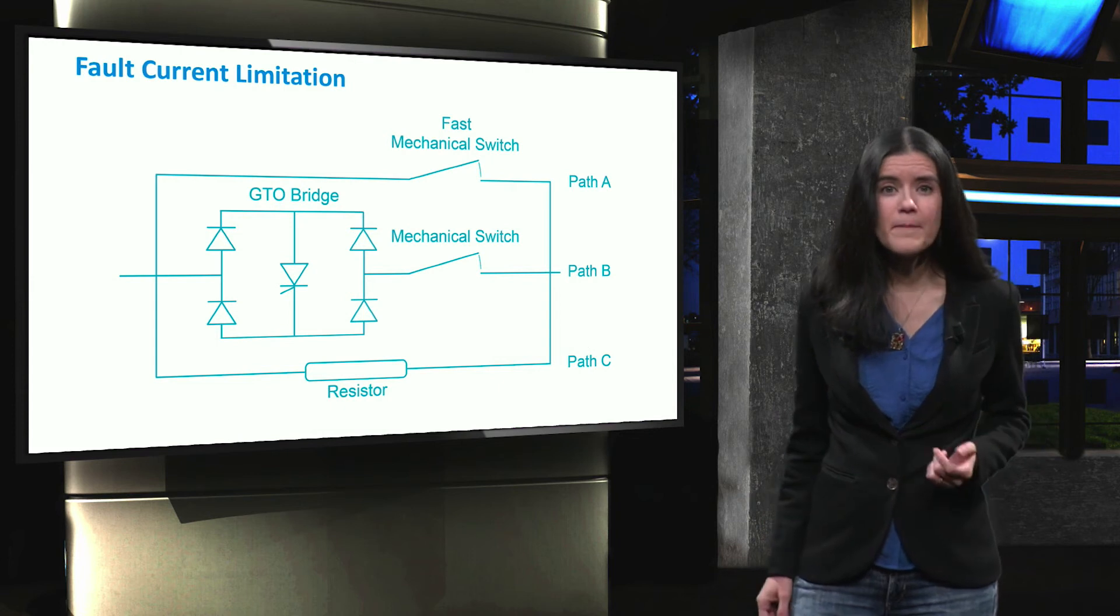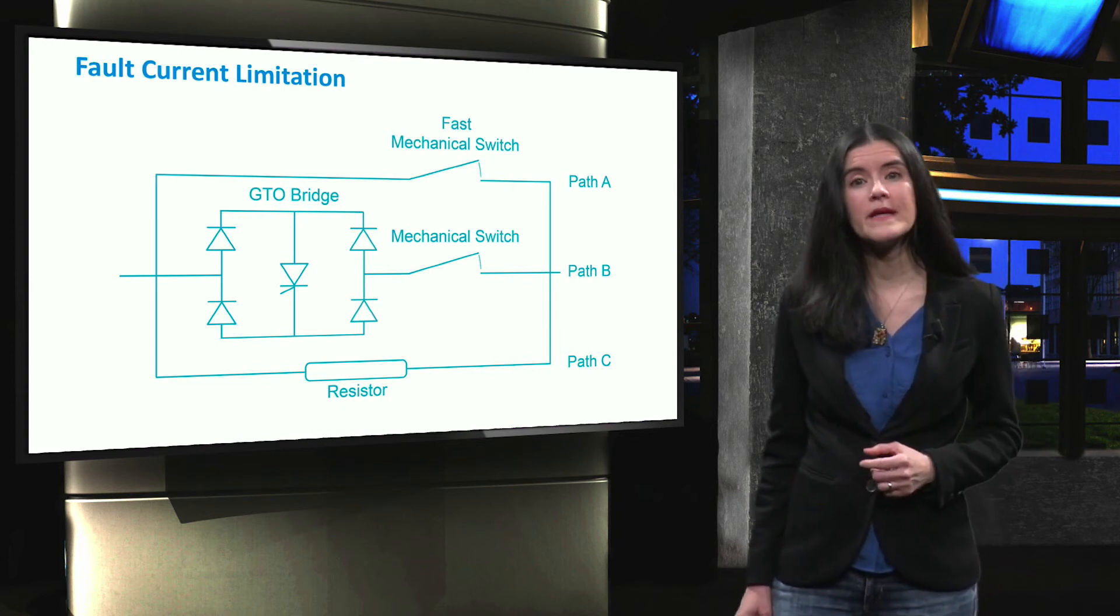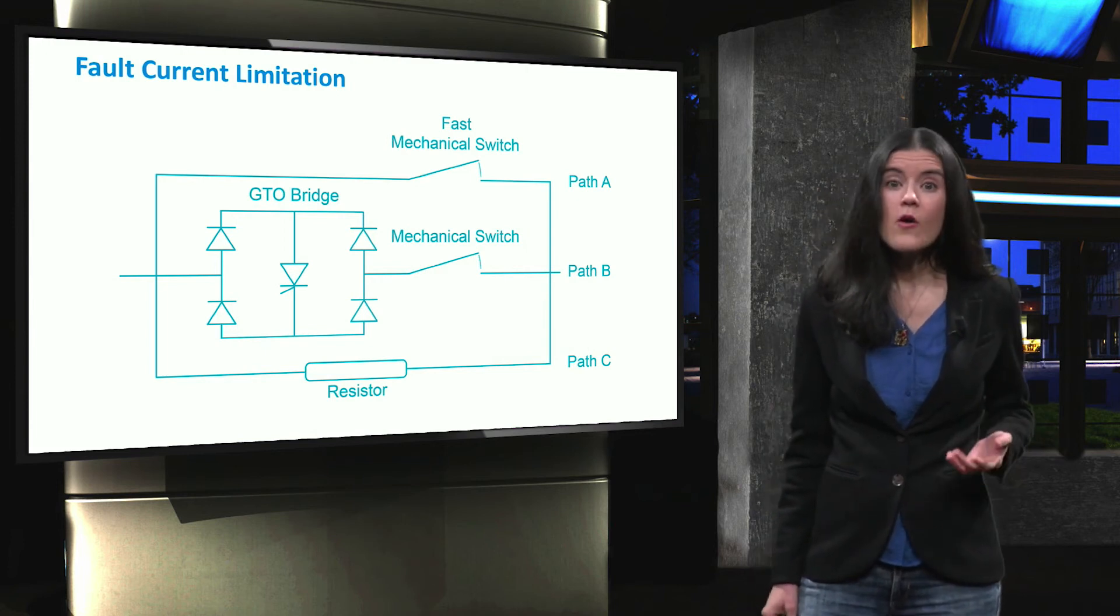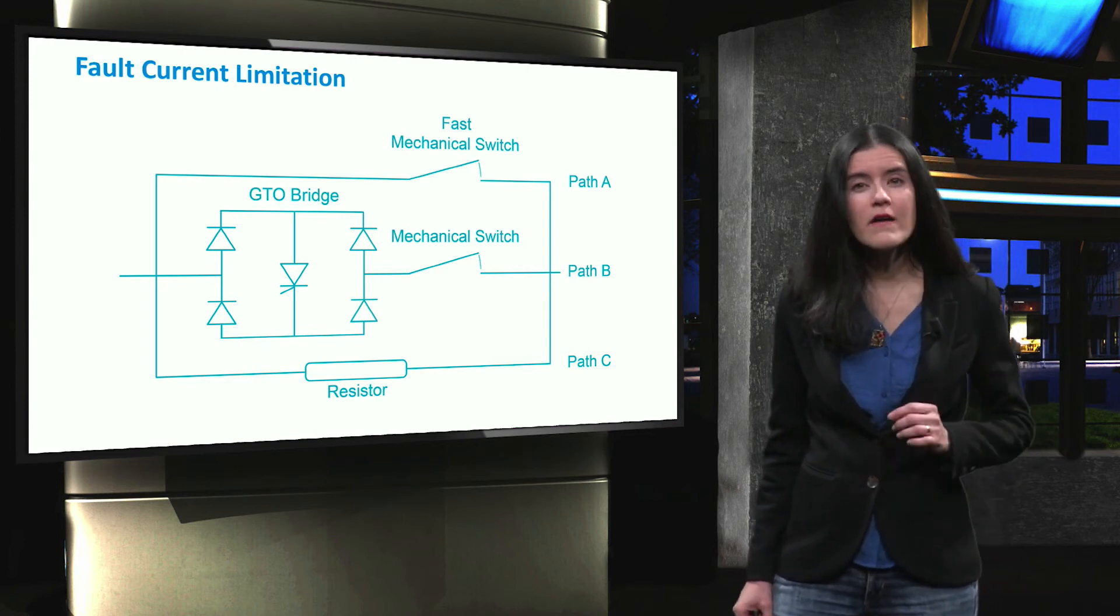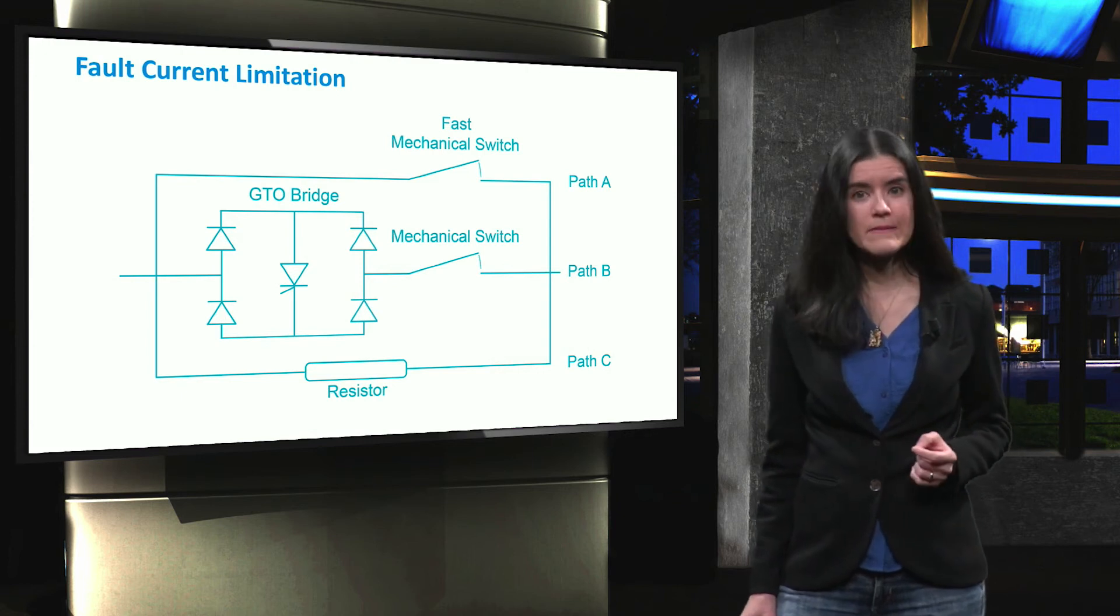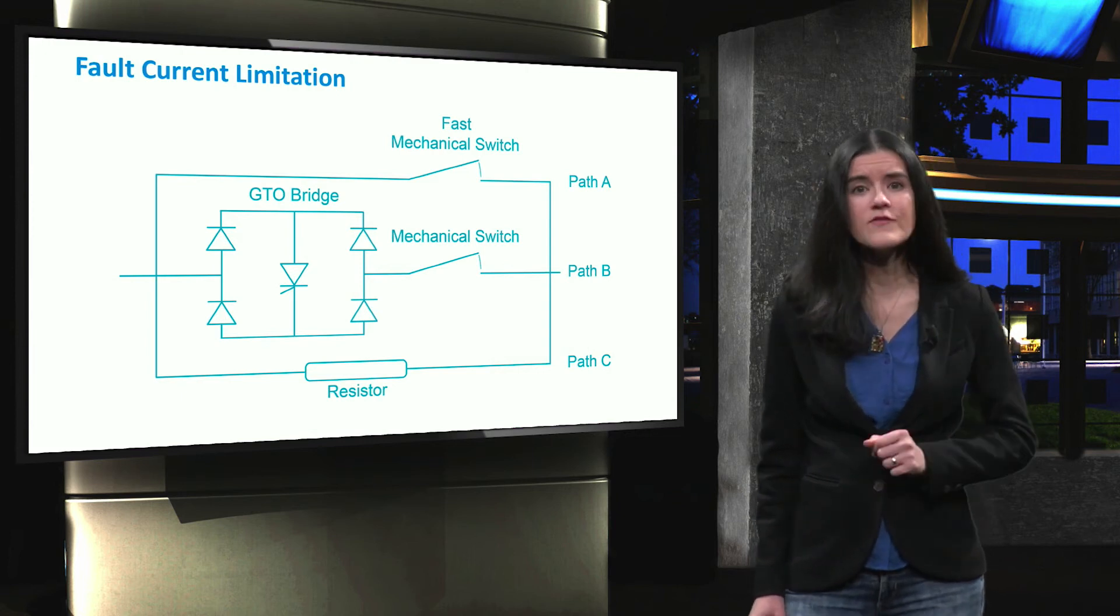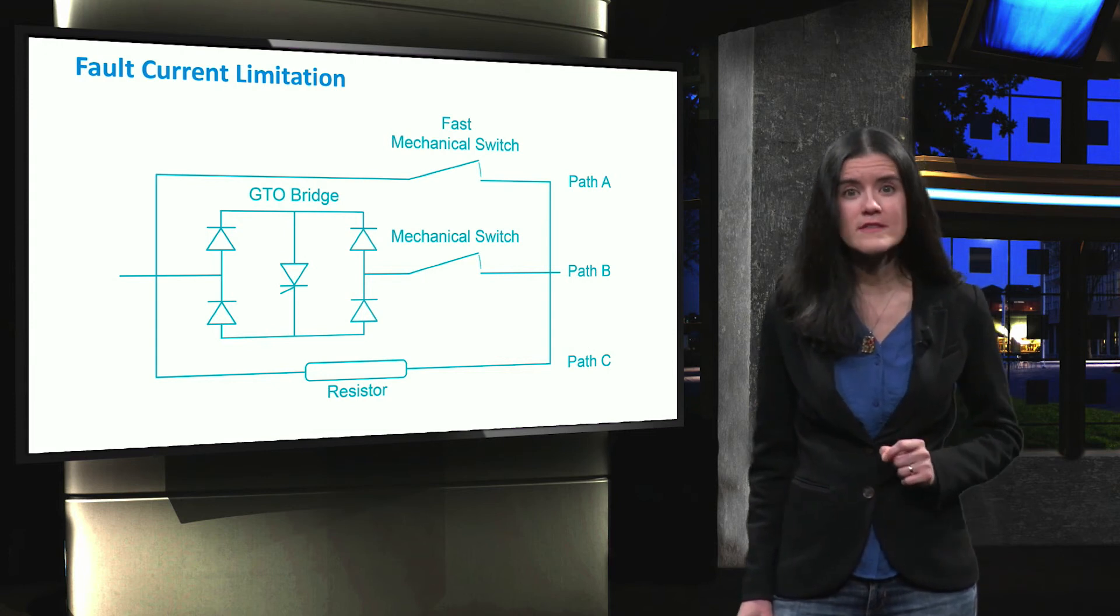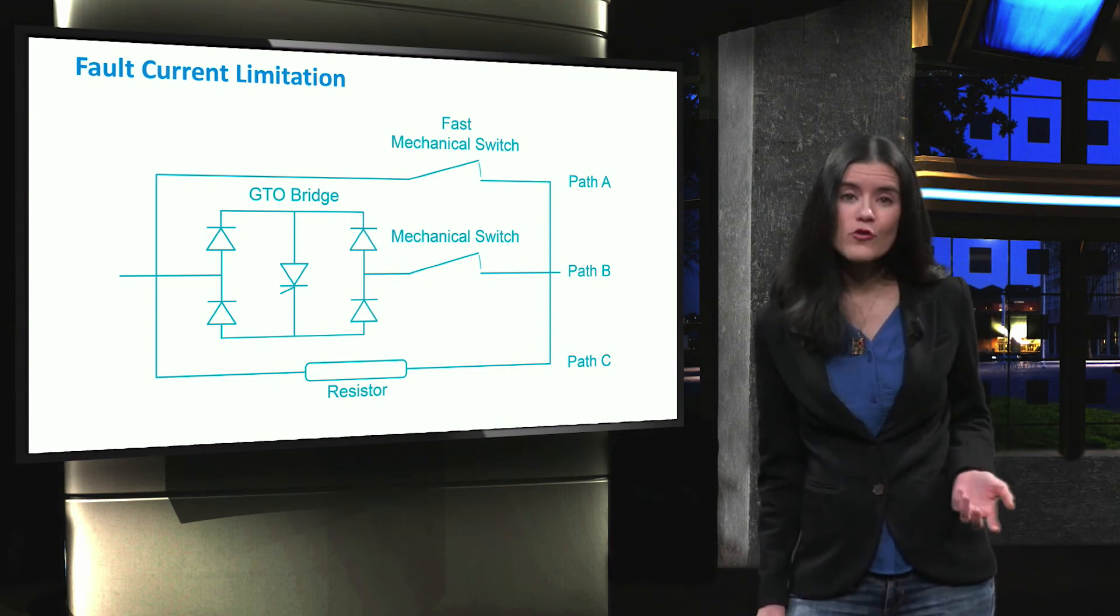Passive solutions are based on having equipment with an increased current path impedance at both nominal and fault conditions. Transformers with increased short circuit impedance are an example of passive fault current limiters. A disadvantage of this solution is that the increased impedance generates losses and a voltage drop during normal operation.